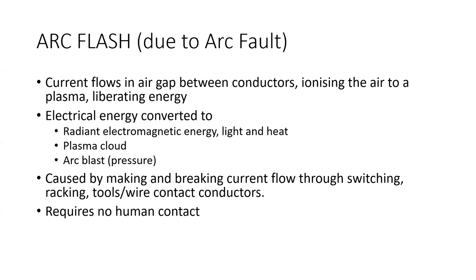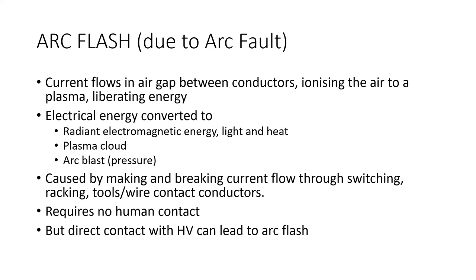An important feature to note is that arc flash doesn't require any human contact, although direct contact with high voltage can lead to arc flash. And I mentioned last month a case I'd investigated where the victim had come in contact with an 11 kV overhead cable by carrying a piece of pipe. And it was found that the electricity actually arced over the skin surface, which caused severe external burns outside the skin, but the skin didn't actually conduct to cause any heart disturbance.